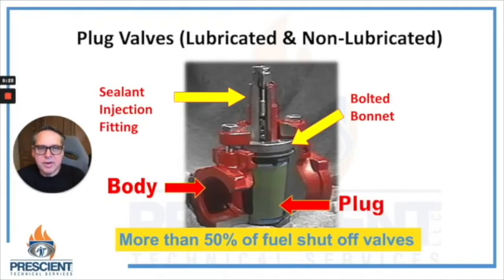There are two primary types of plug valves: lubricated plug valves and non-lubricated plug valves. Non-lubricated plug valves typically have some type of resilient seal that actually mates with the plug and touches it. Lubricated plug valves have no such seal internally — they rely on a sealant that gets injected down through the top via what's called a button head fitting. This sealant has to find its way around all of the surfaces of the plug — on top, under, and around — and it's only the sealant that makes the valve function as an isolation valve.